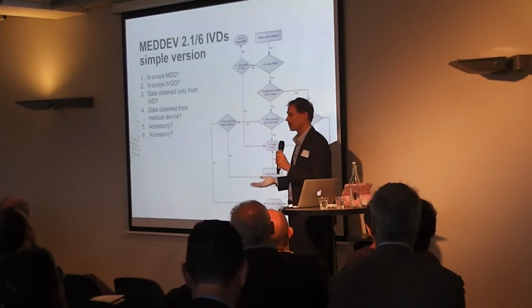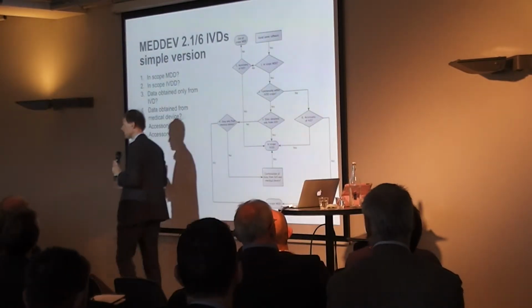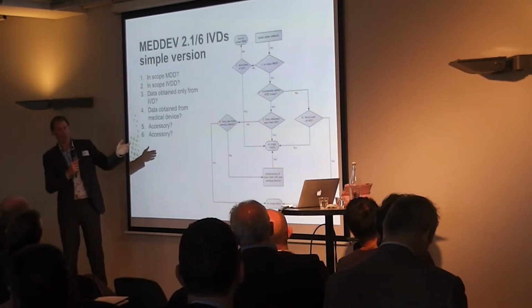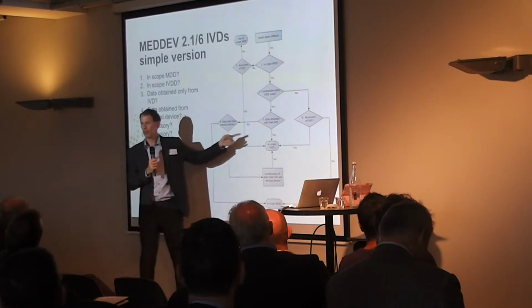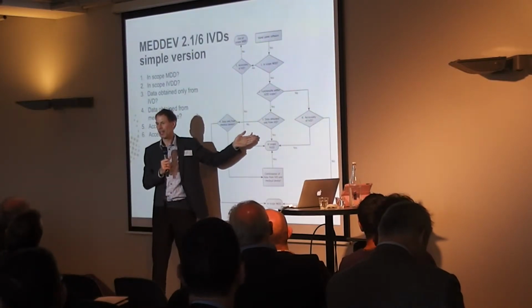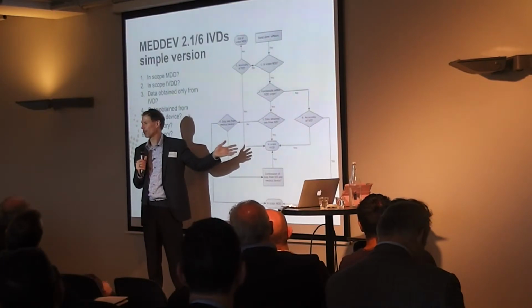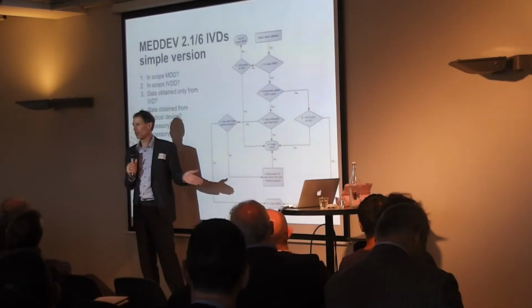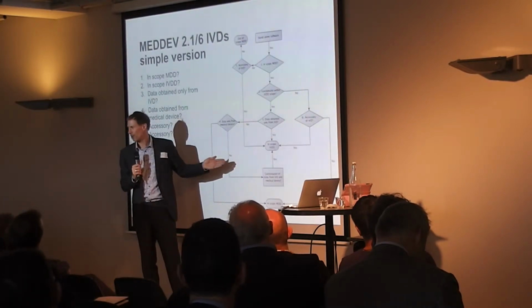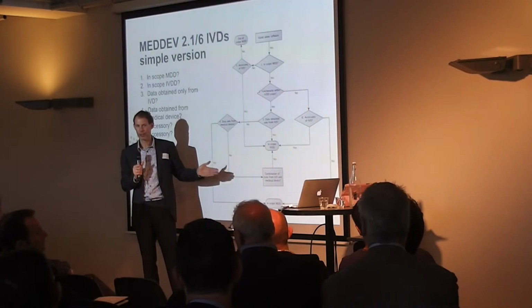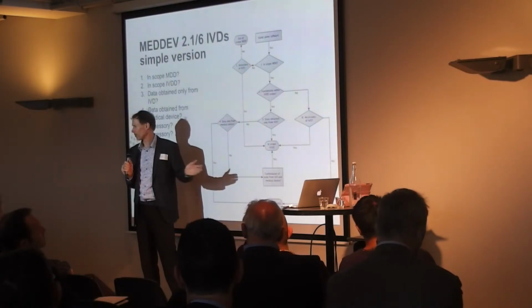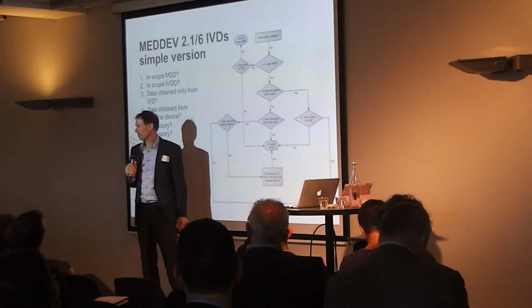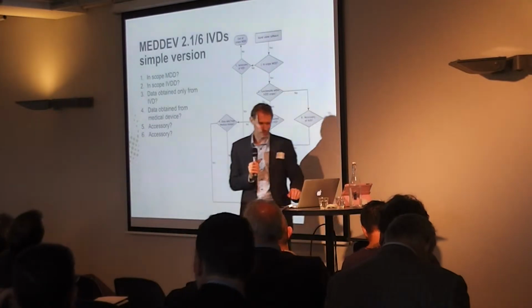Once you are in the scope of the Medical Devices Directive, if you have software that specifically works with in vitro diagnostic data, data that comes from an in vitro diagnostic device like a blood glucose meter, you have to seriously consider that your software can be an in vitro diagnostic device and needs to be CE marked under another directive than the Medical Devices Directive. It's a directive that looks a lot like it, but still has different criteria. So be careful of that.